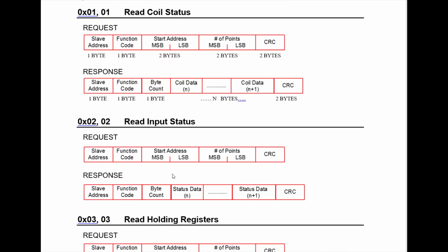And in the slides, we're looking at a 02. So we're looking at a 02, first identifying the function code for the request, and then dropping each one of those 2 hexadecimal numbers into each one of these boxes till we're done, and we're ending off with a 2 byte CRC.